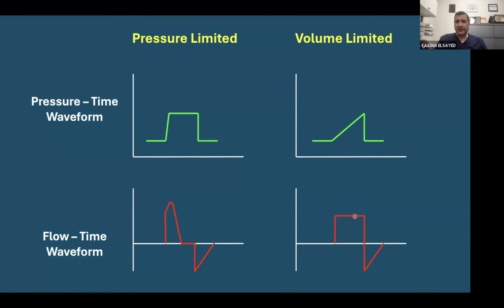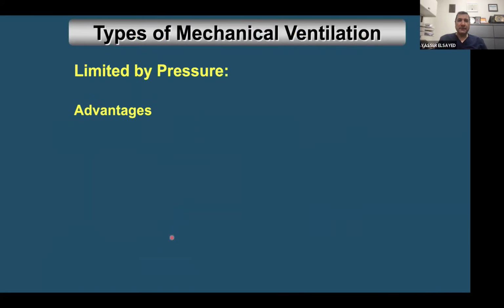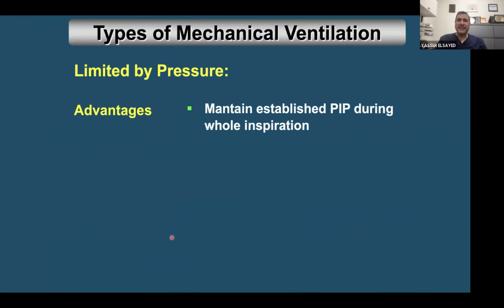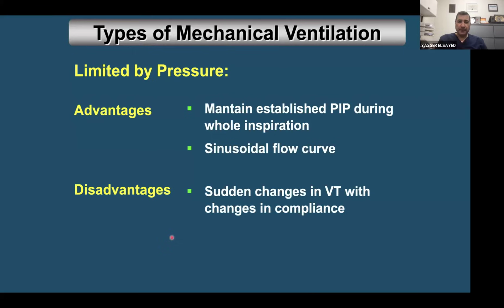So we have fixed volume delivered during the inspiratory time, or fixed flow delivering specific volume, but it's not the case here. It's a little bit variable according to the lung compliance. So limited by pressure advantages, maintain established PIP during the whole inspiration. Sinusoidal flow curve is not rectangular, it is sinusoidal, and you may have sudden change in tidal volume with a change of compliance.